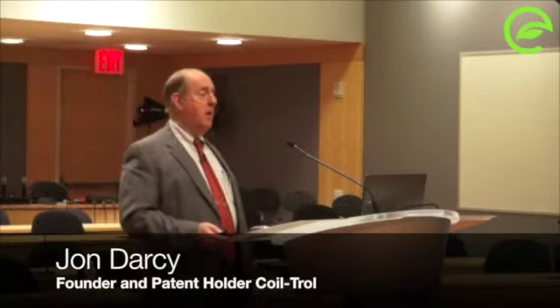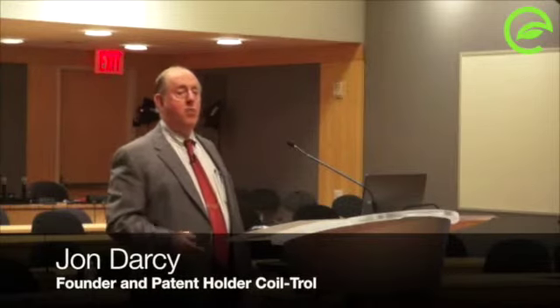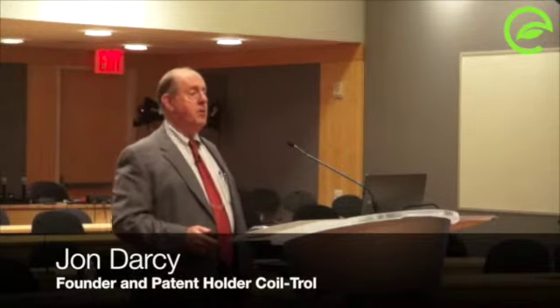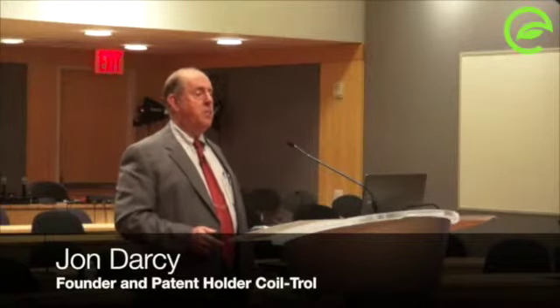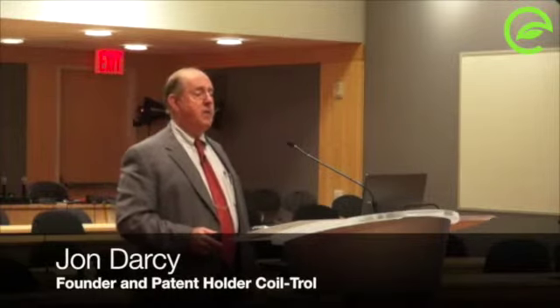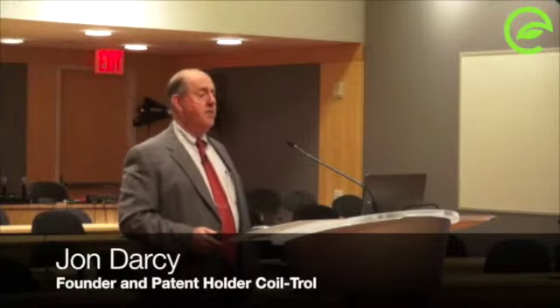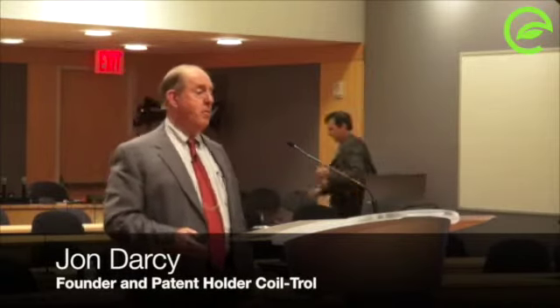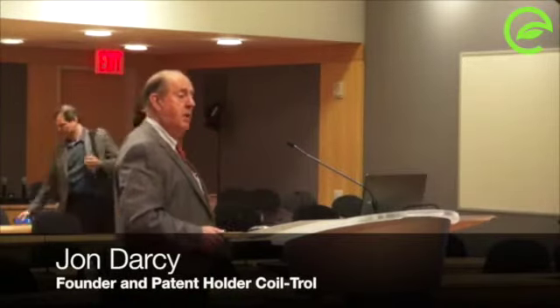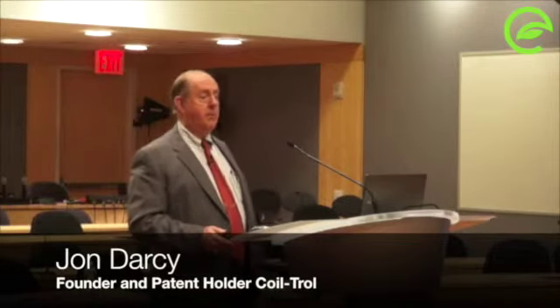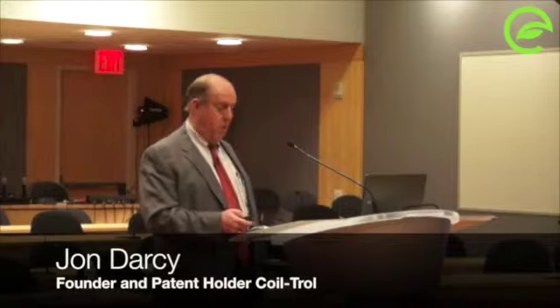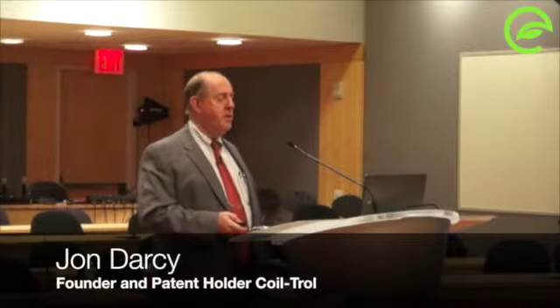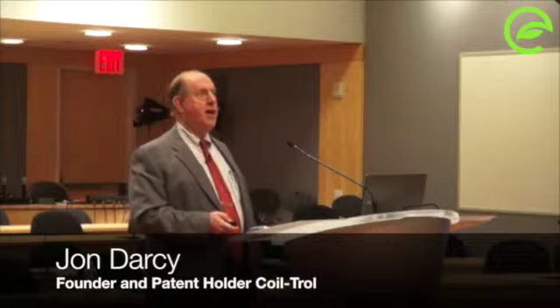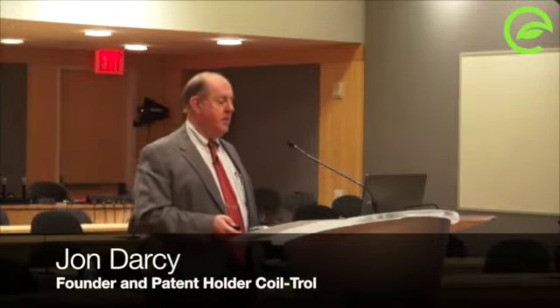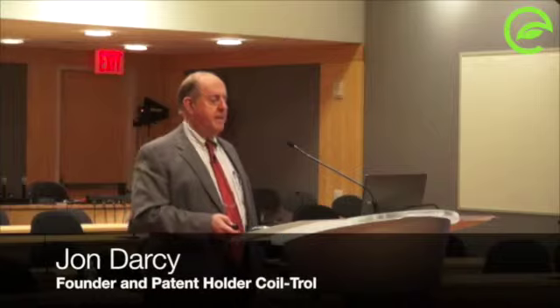And in fact, when Kieran over here worked for Wyeth, we did a group of maybe 20 critical temperature and humidity rooms and held the temperature plus or minus a tenth of a degree and the humidity plus or minus 0.5%, 24/7, 365. Okay, so it can be done, but it required some different type of control. So what I wanted to do was, when I was designing air handling units for a while, I was selling and designing custom air handling units.